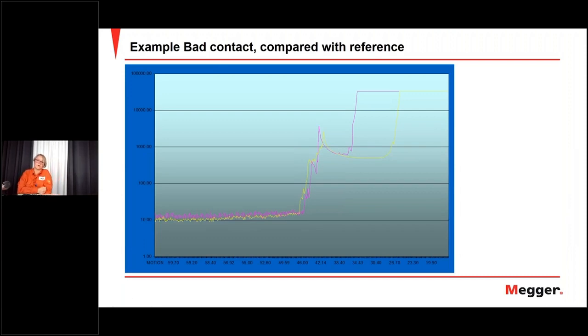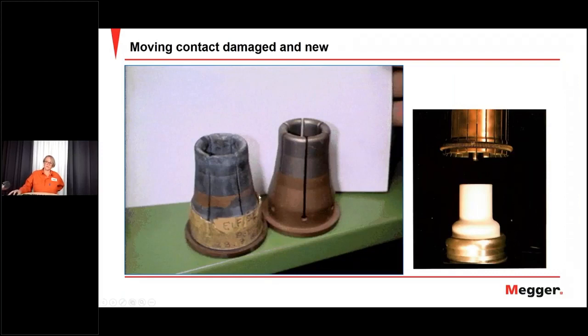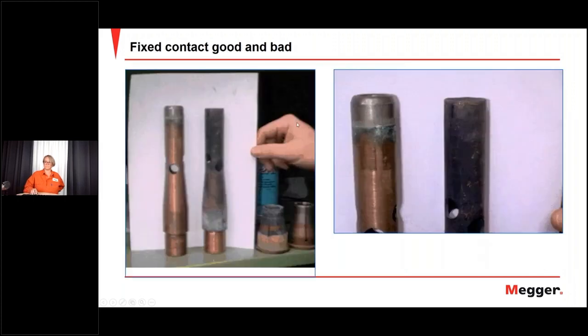Here we have put two graphs on top of each other. It is the yellow as new and the pink after really tough breaks. So here, this graph has all of a sudden changed much earlier. And this is how it looked. This is the arcing contact in well overused shape, I would say. And this is how it looks when it's new. Here you have the fixed arcing contact, the new and the old. And here you see a detail of the same.